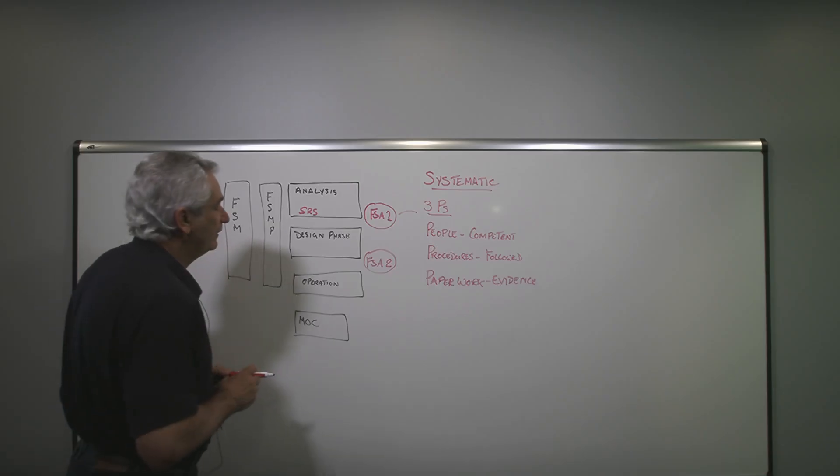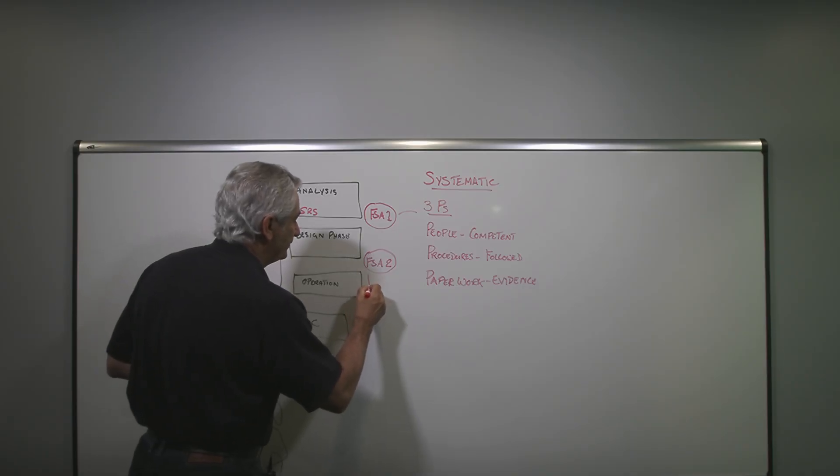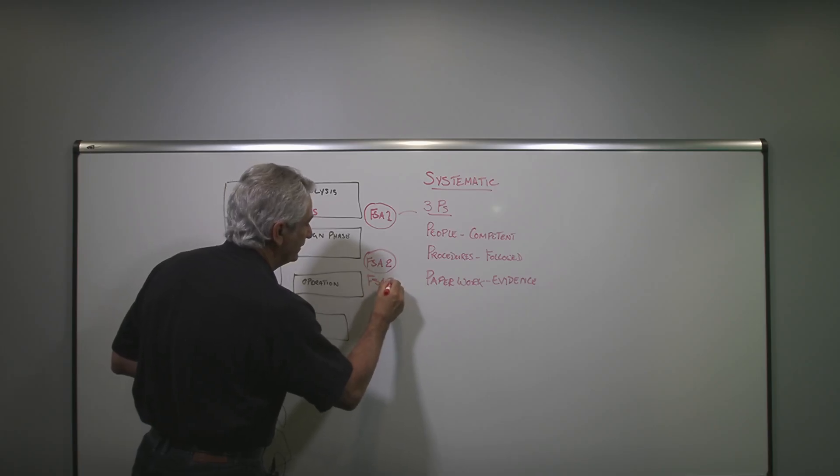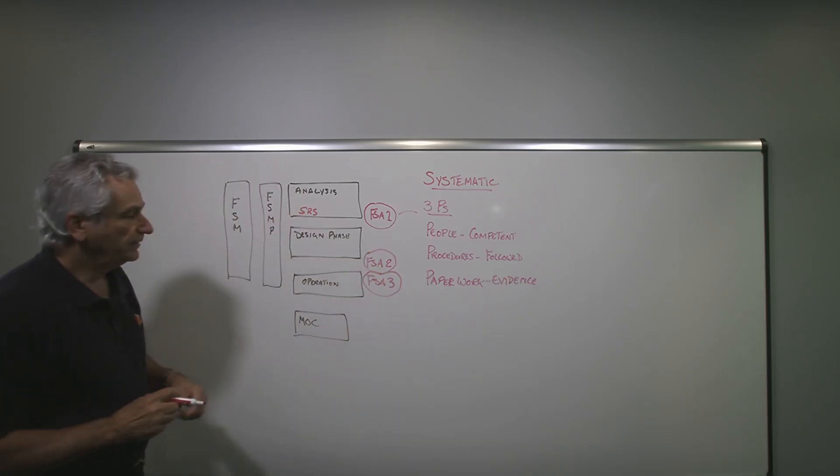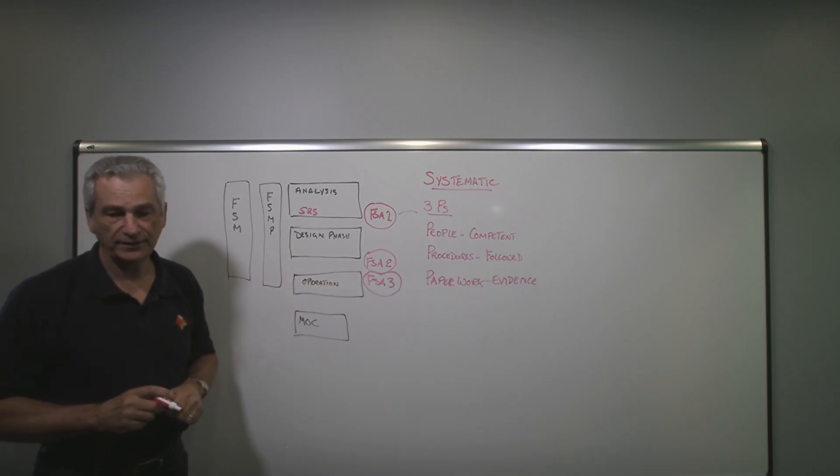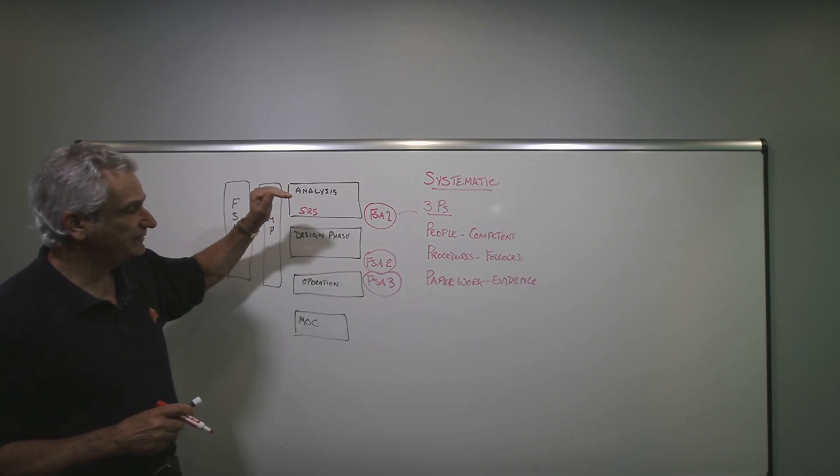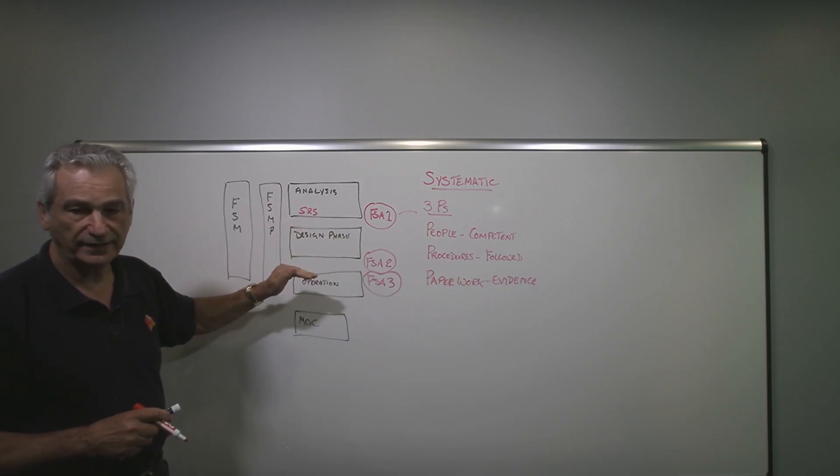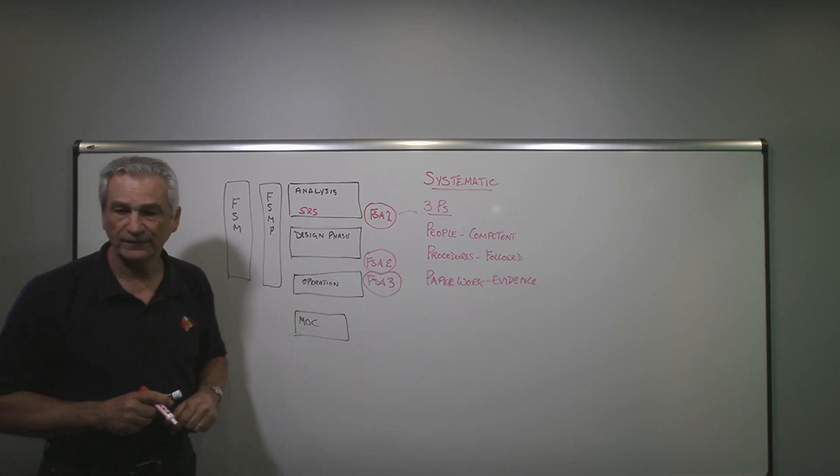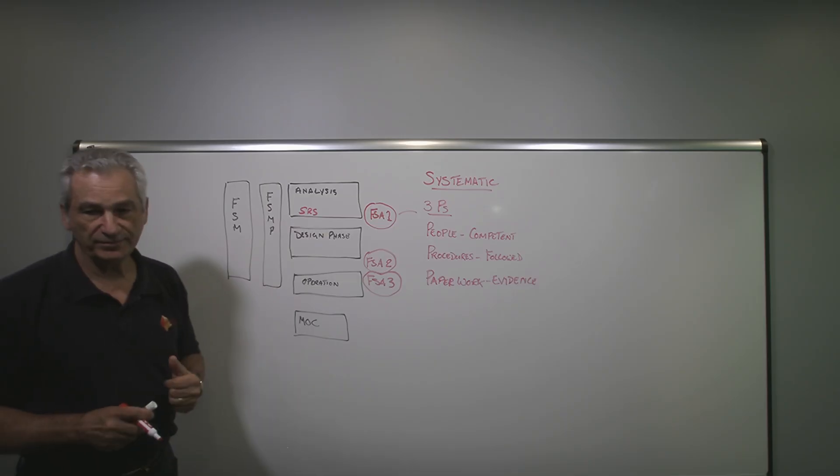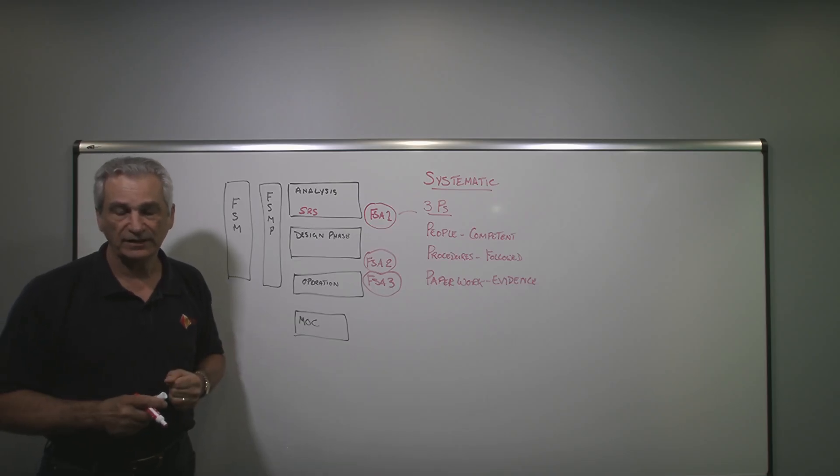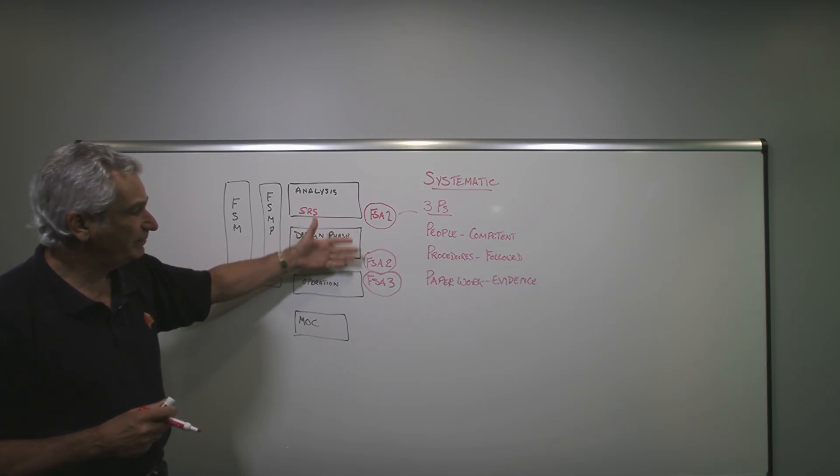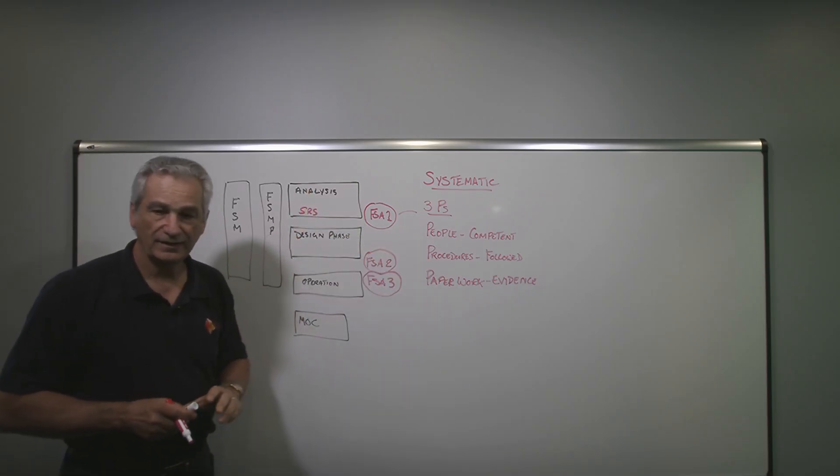Then, before we start up, we have to do an FSA-3. After the installation and commissioning has been done, we have to do an FSA-3. So this is the first mandatory one, according to IEC 61511. The purpose of this, of course, is to make sure the as-designed, installed, and commissioned SIS and its SIFs meet all of the safety requirement specification. The same thing: do we have what we need from safety? Do we actually achieve safety? Do the safety instrumented functions perform their tasks properly and achieve safety? And are there any potential systematics that we may have missed, according to these three?